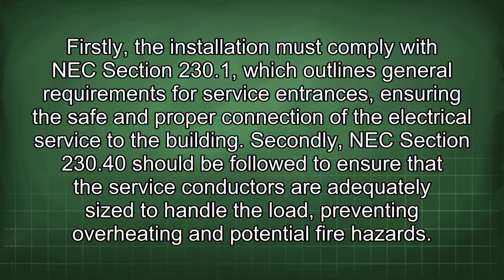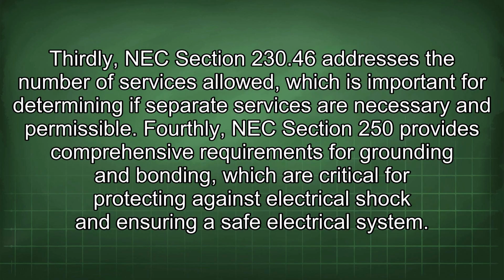Secondly, NEC section 230.40 should be followed to ensure that the service conductors are adequately sized to handle the load, preventing overheating and potential fire hazards. Thirdly, NEC section 230.46 addresses the number of services allowed, which is important for determining if separate services are necessary and permissible. Fourthly, NEC section 250 provides comprehensive requirements for grounding and bonding, which are critical for protecting against electrical shock and ensuring a safe electrical system.